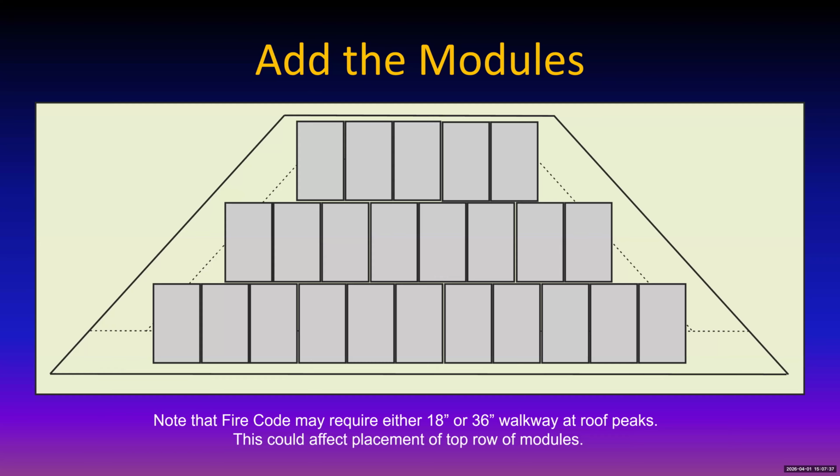So you may have to lay these things horizontally, and if you have to do that, you're only going to be able to put maybe 4 or 3 instead of 5 of them up there. But in any case, we're trying to keep away from the edges because if you get too close to the edge, that's an extra 50% increase in pressure. And that sometimes gets to be a little nasty in terms of mounting. But a lot of places you can get up to the edge. But if you can avoid it, you try to avoid it.